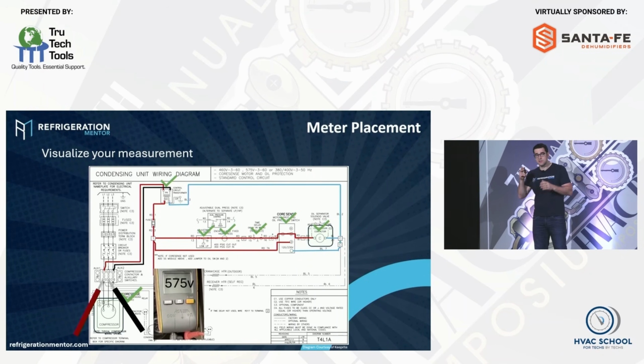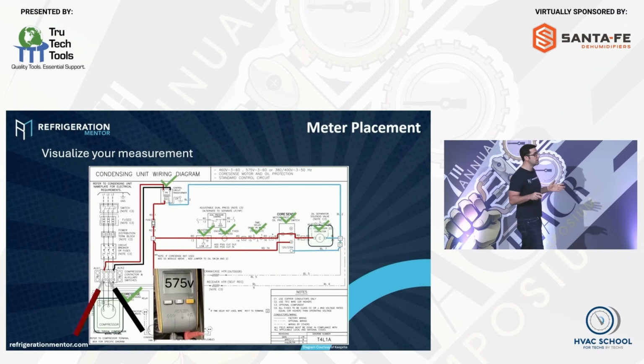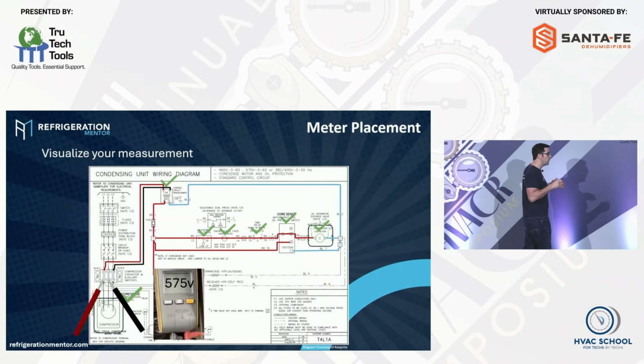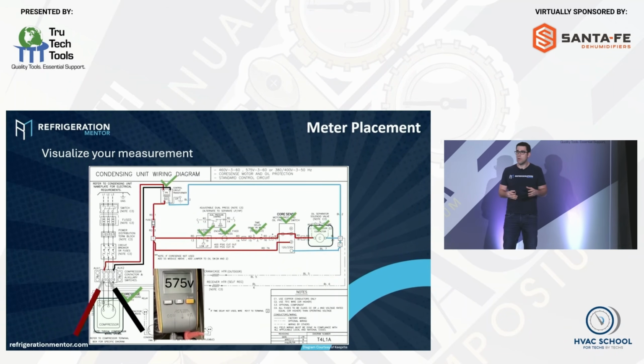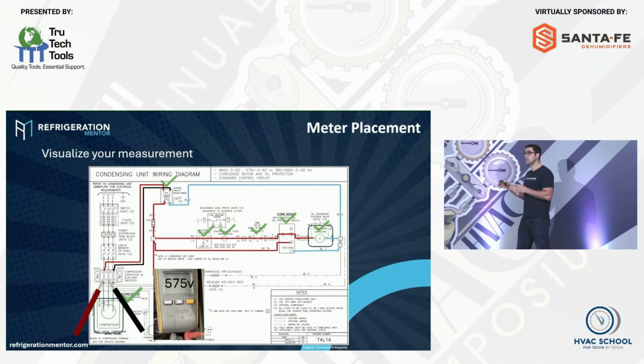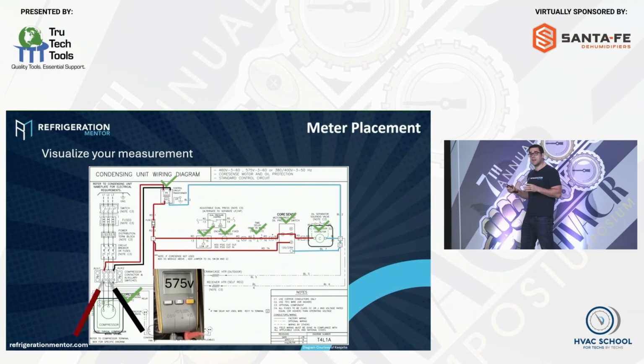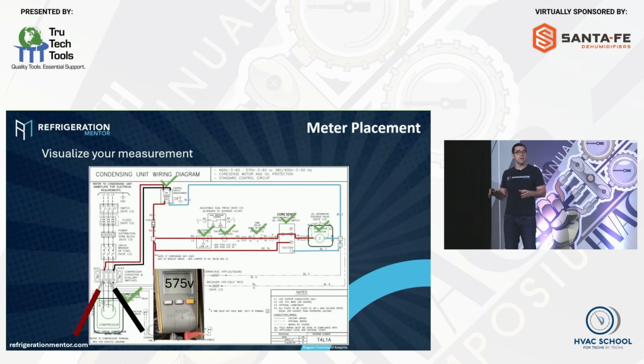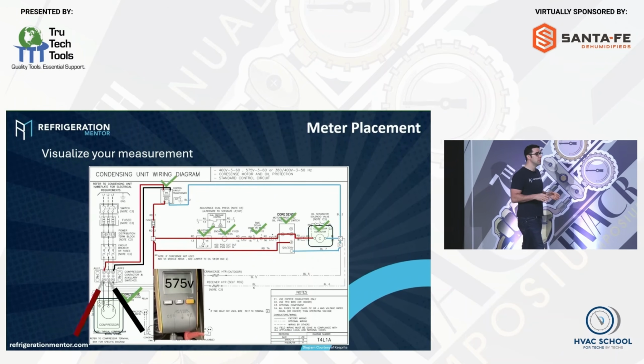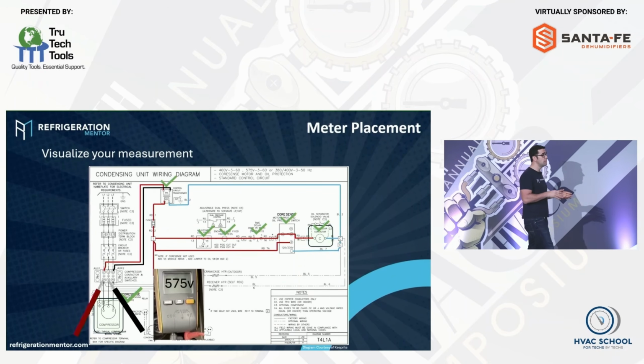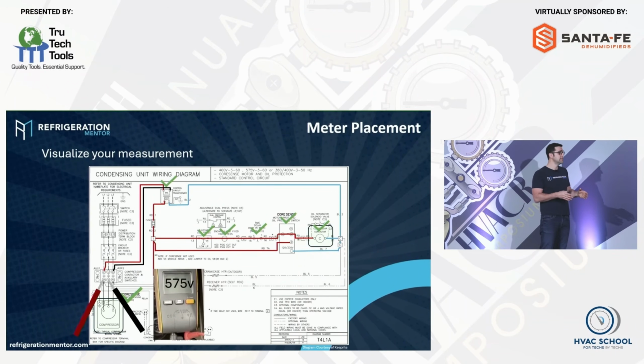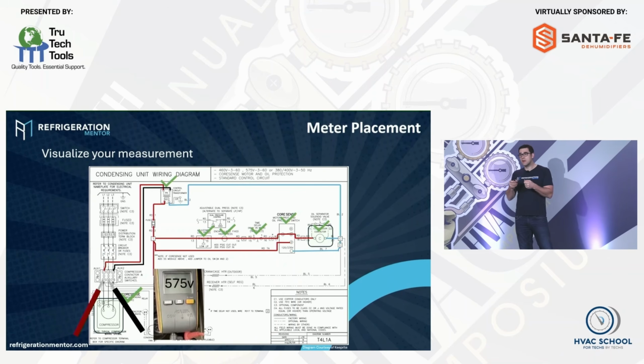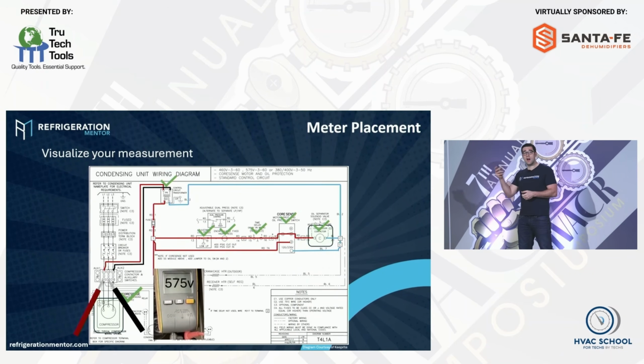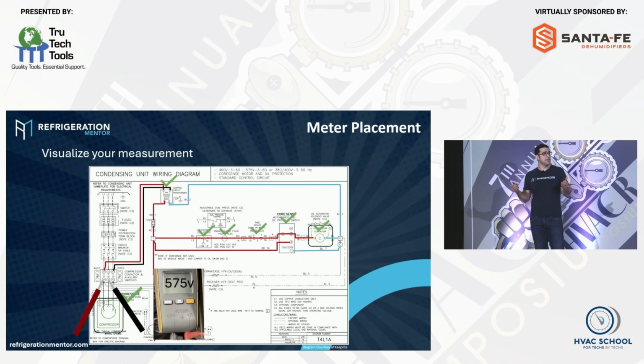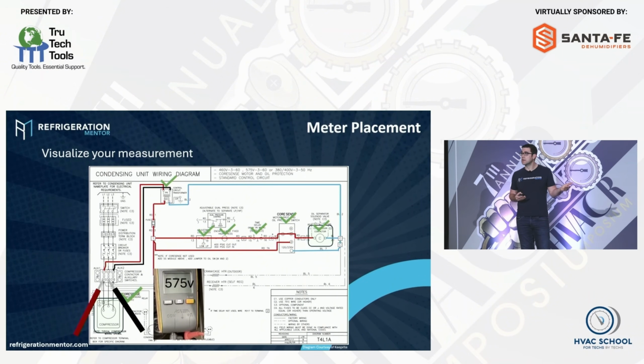We need to visualize. The more you read these, this is how you're going to get better. Like in my supermarket program, one of the main things we're doing is reading electrical wiring diagrams, getting the diagrams, and walking through them step by step. Because if you're not doing this every day, you're not going to get better very quickly. But if you're doing this every day, you're going to be able to troubleshoot systems that you have not troubleshot before, because it takes consistency, it takes practice, and getting your meter out there. You should be able to visualize this. When someone says the contactor's not pulling in, you should be able to think, well, the coil must not have power. Right? That's one of the things you would think of. You've got to visualize this stuff.